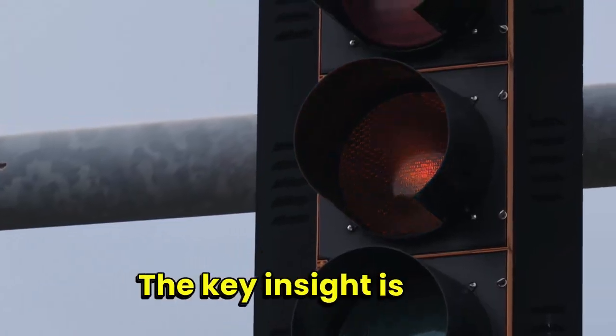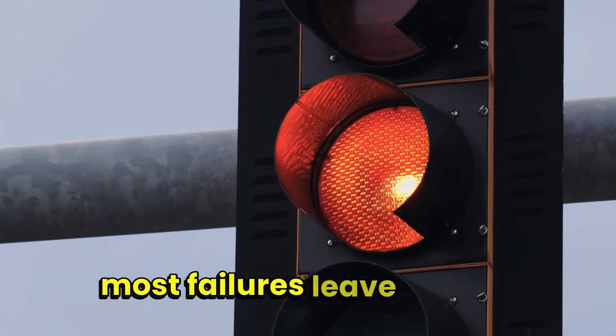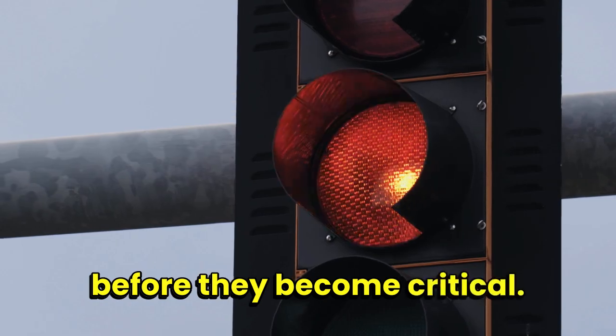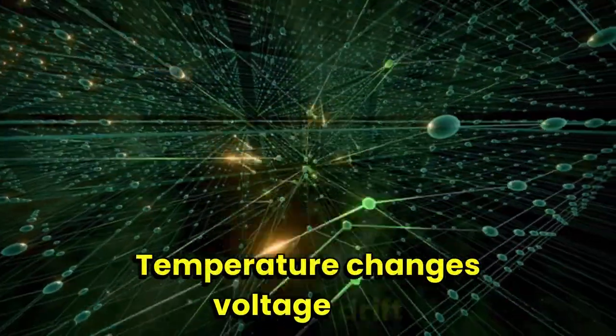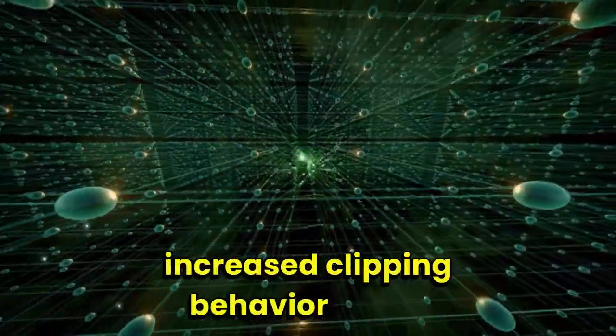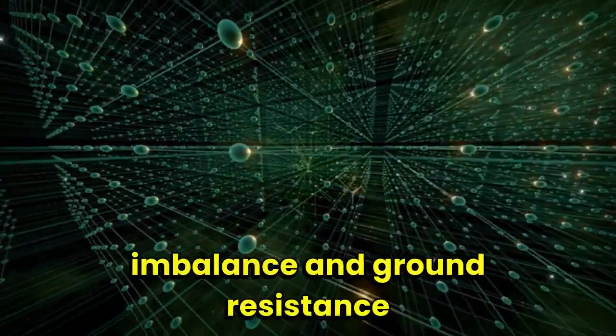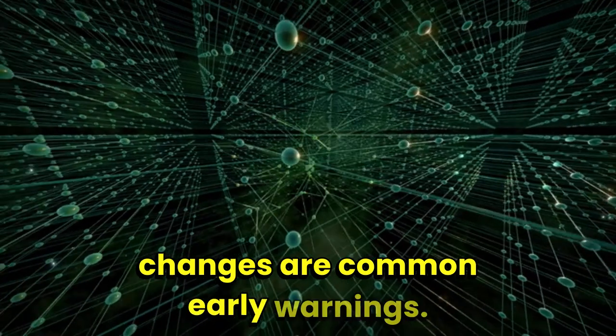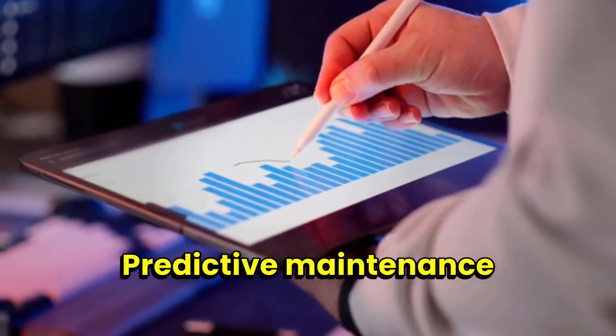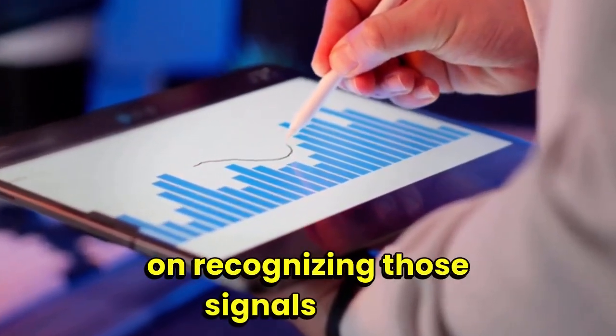The key insight is this: most failures leave signals before they become critical. Temperature changes, voltage drift, increased clipping behavior, string imbalance, and ground resistance changes are common early warnings. Predictive maintenance depends on recognizing those signals early.